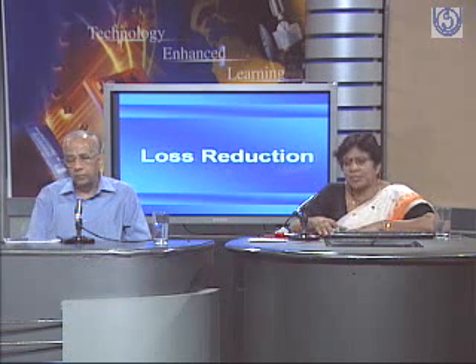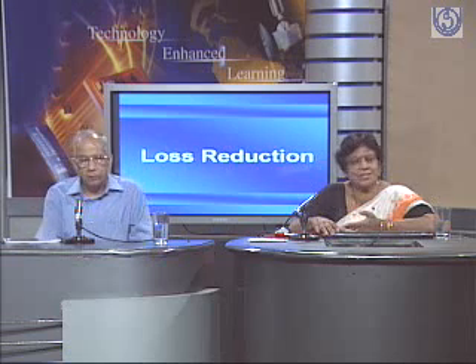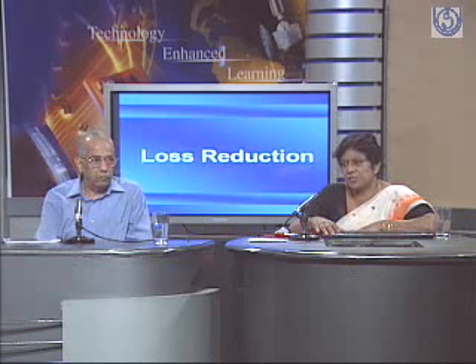And if the multiplier factor is not proper, then your bill is definitely going to change. You have to use the proper multiplying factor. If your reading was to be multiplied by 10, and you multiply it by 1, then naturally you are going to charge for one-tenth of the amount.